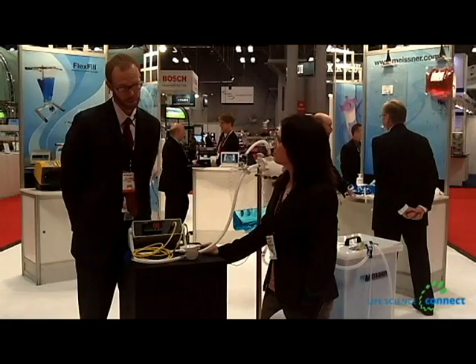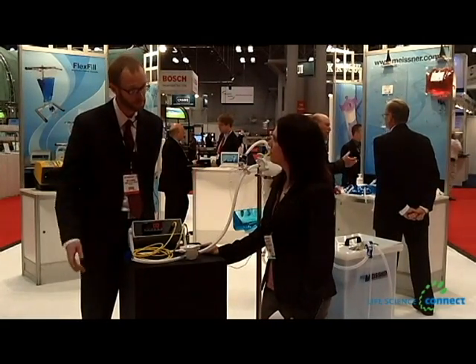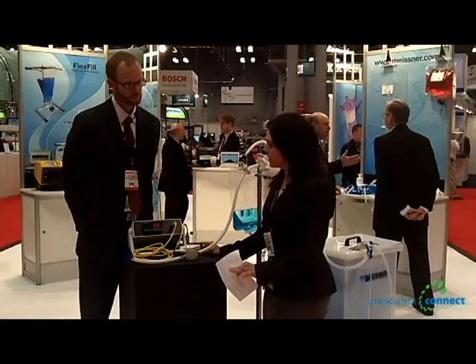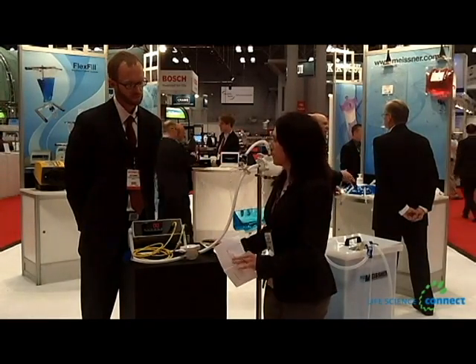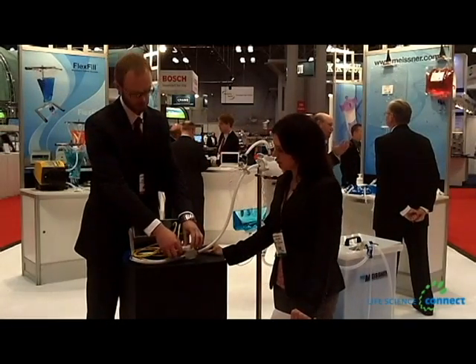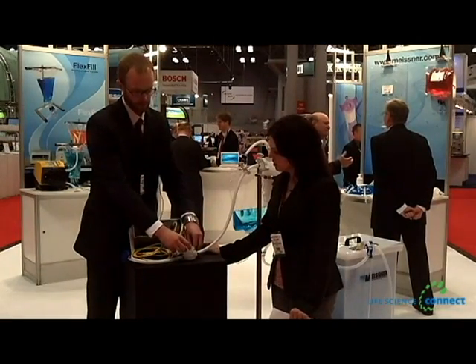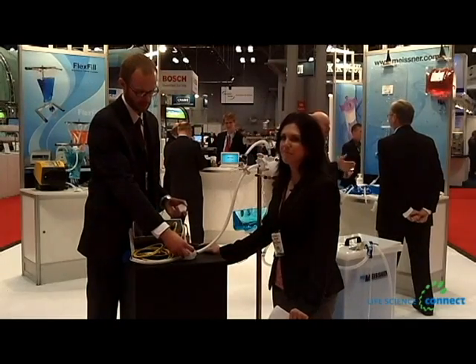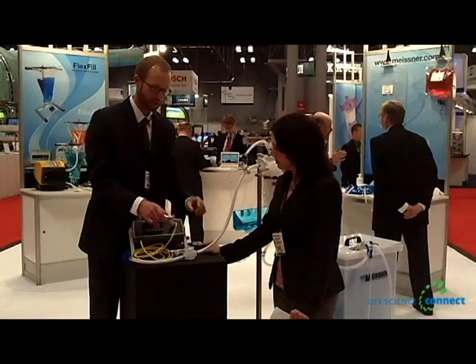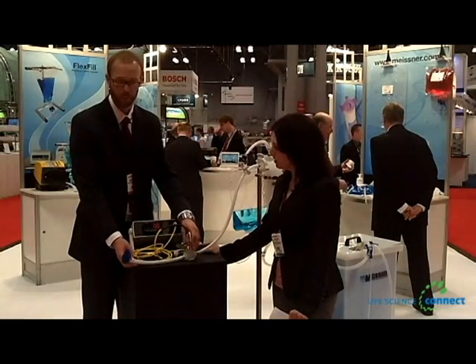We're showcasing a number of technologies here at Interphex this year that really ease the implementation and robust implementation of single-use systems. One of the technologies right in front of me here is what we're calling a single-use gauge T. What this allows end users to do is to aseptically add a diaphragm pressure gauge to your fluid path. What you see here is a polypropylene housing with a thermoplastic elastomer diaphragm welded to the top, thermally welded, permanently welded, and this allows you to add a diaphragm pressure gauge to your fluid path aseptically, so without breaching sterility.